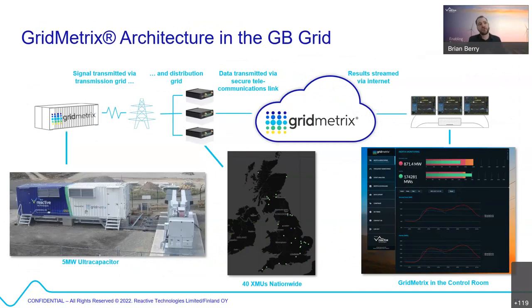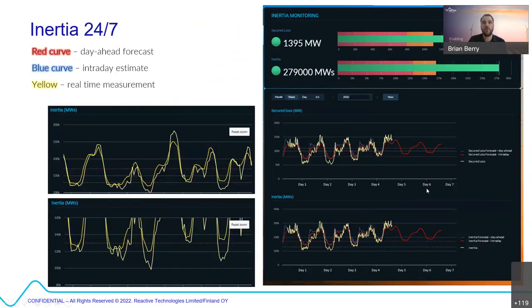Now, talking about National Grid, very similar, except a lot bigger. As I say, 20 to 60 gigawatts demand. Here, the modulator is a 5 megawatt ultra capacitor. Why? Because ultra capacitors can cycle without degrading as much as batteries. We've got frequency measurements all around the grid, 40 measurements, again coming into that platform.